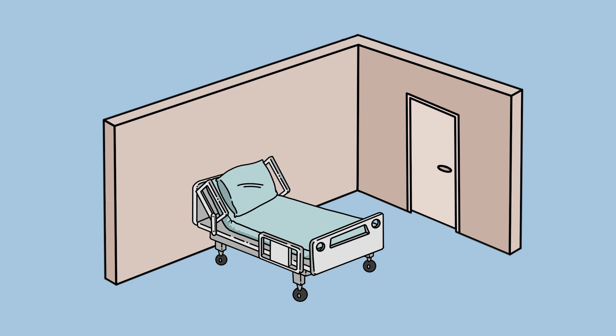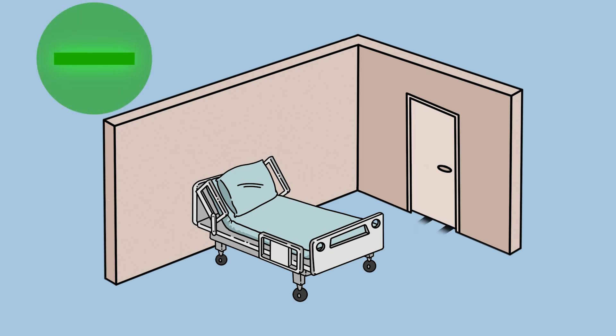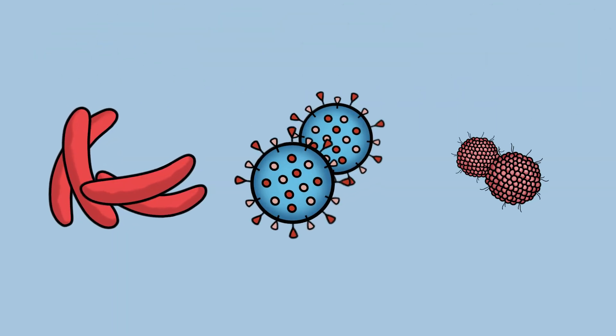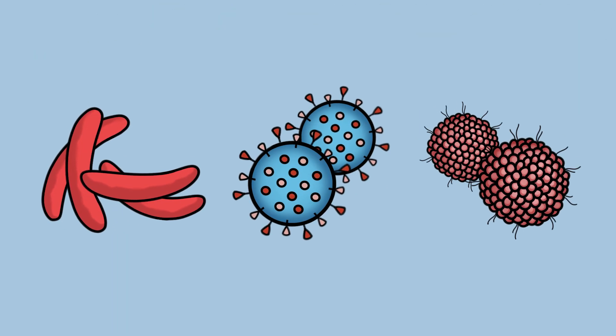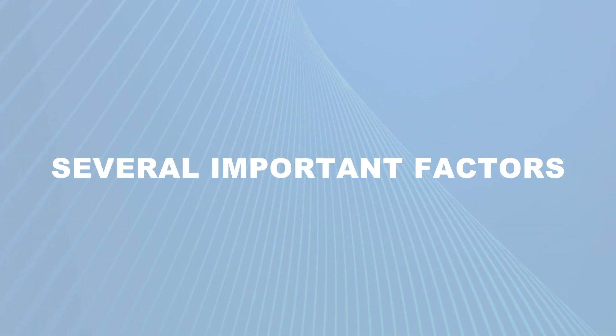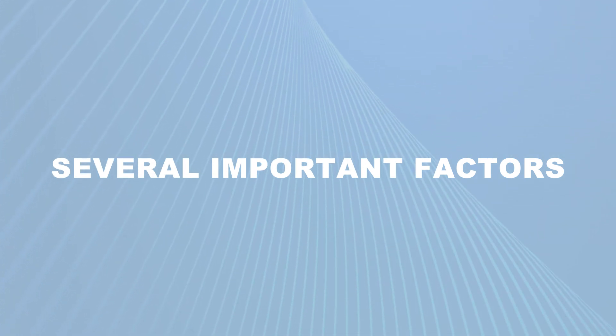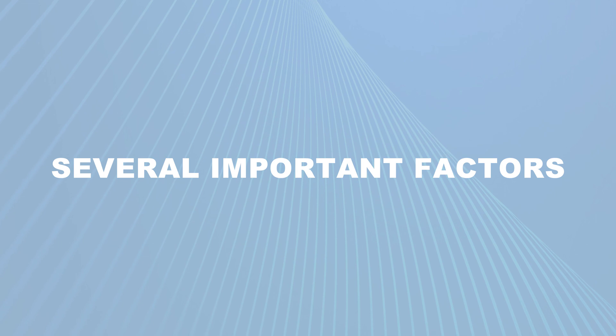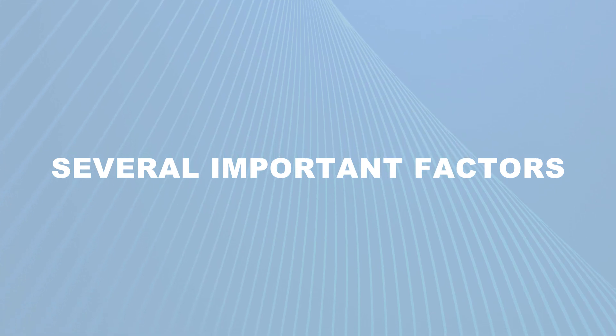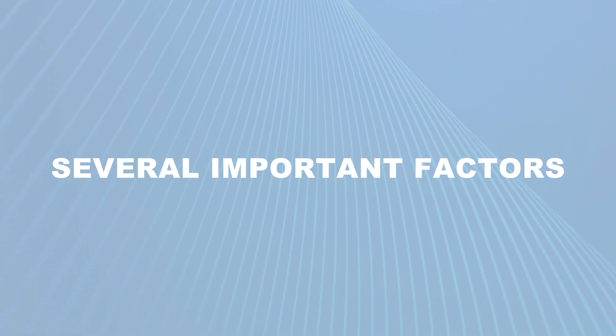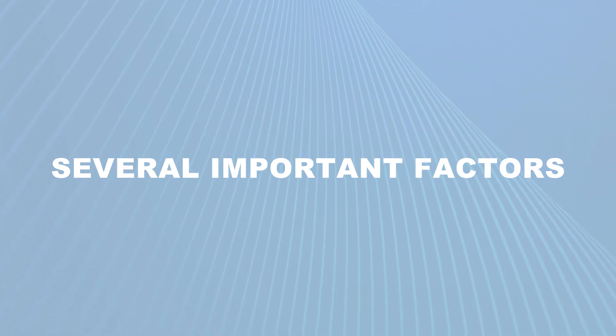AII rooms are special rooms that are always sucking air in from surrounding areas, making them negative pressure rooms. They are designed for patients who have a known or suspected airborne infection such as tuberculosis, measles, or chickenpox. There are several important aspects of AII rooms that facilities operations personnel must understand to ensure that everyone in the building remains safe and that patients are getting the best possible care.